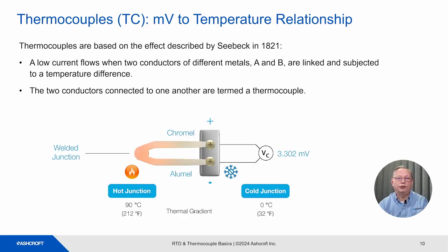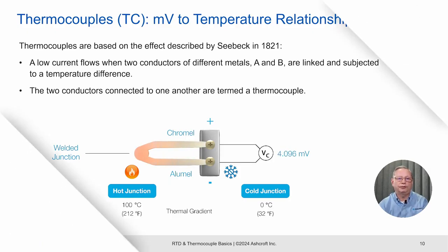If we lower the temperature at the other end of the thermocouple wires, termed the cold junction, to 0 degrees C, we have a temperature difference of 100 degrees C, which for this K thermocouple will produce a 4.096 millivolt signal. The cold junction is normally referenced to 0 degrees C. This is referred to as cold junction compensation. This is done by the circuitry in the temperature transmitter or PLC with the thermocouple input.